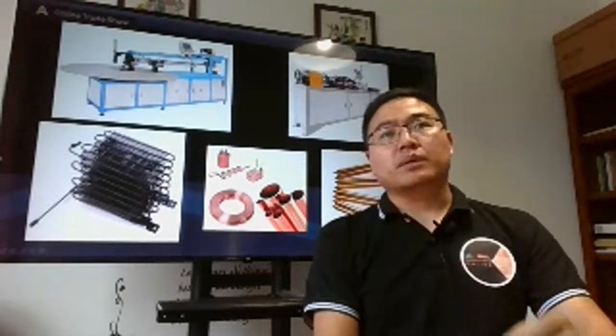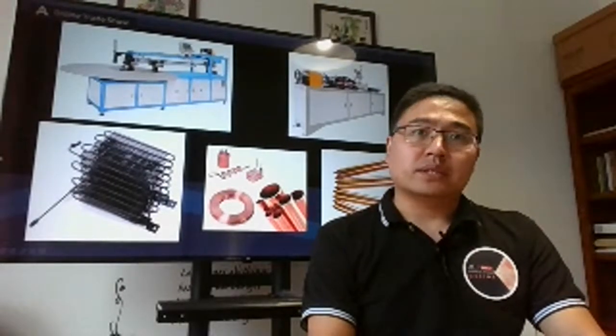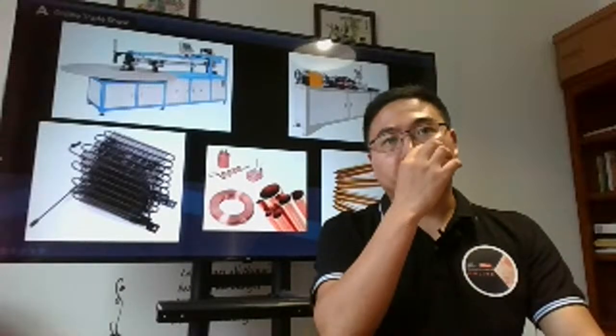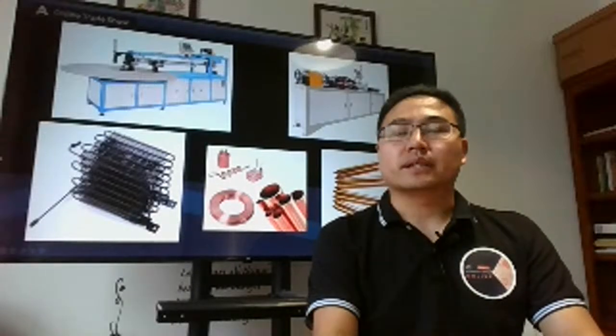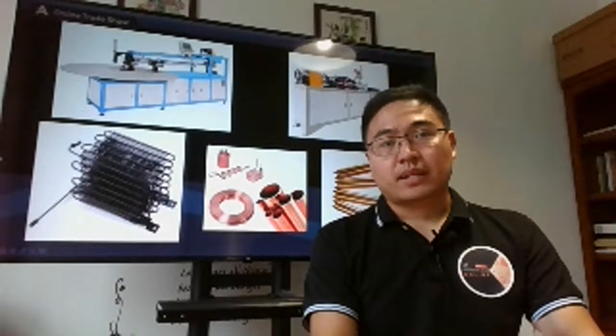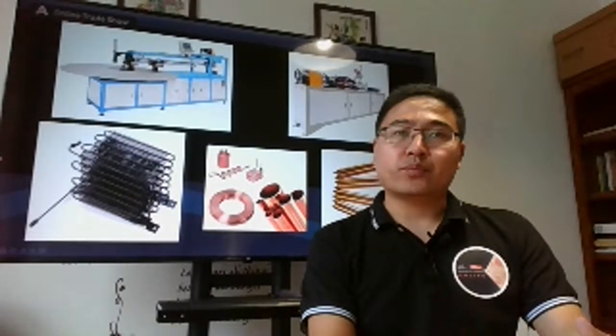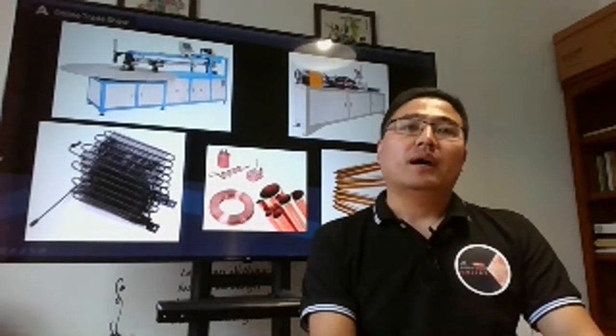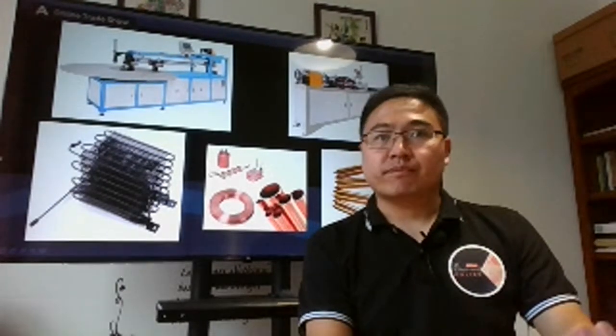The tubes will be straightened by rollers and cut using rotary cutting, which keeps the cutting clean - there are no scraps, and the cutting doesn't reduce the tube diameter. So it is very good for refrigeration and heat exchangers for cutting the tube's length.